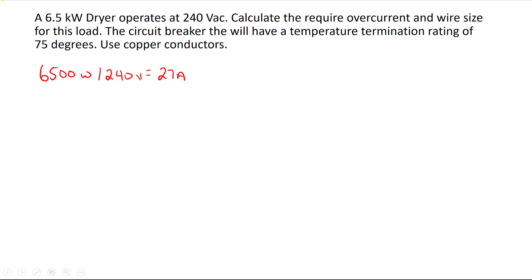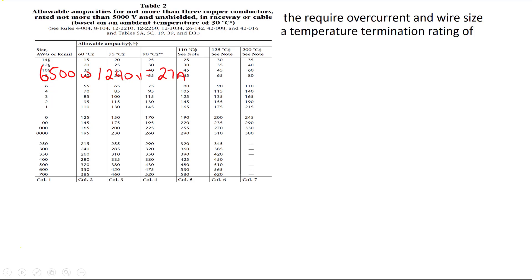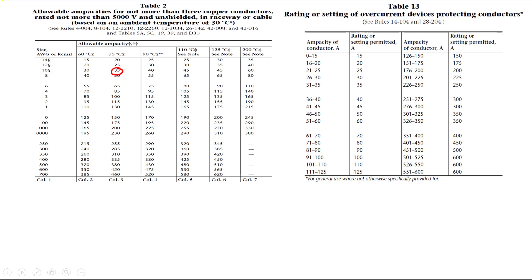Now I can take my 27 amps and select a wire size. I go to Table 2. In the 75-degree column, number 10 is good for 35 amps, so it will more than handle the 27-amp load. Now I go to Table 13, which tells me that if I have a conductor good for 35 amps, I can put it on a 35-amp breaker. However, looking at Table 2 there is a small 'S' symbol that takes me to Rule 14-104, which is also noted at the top of Table 13.